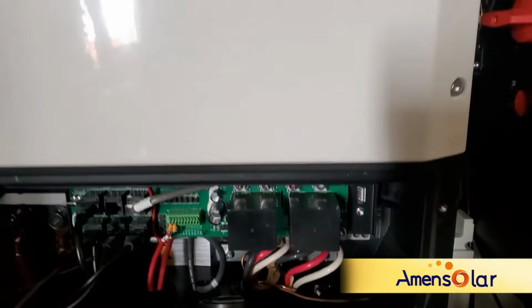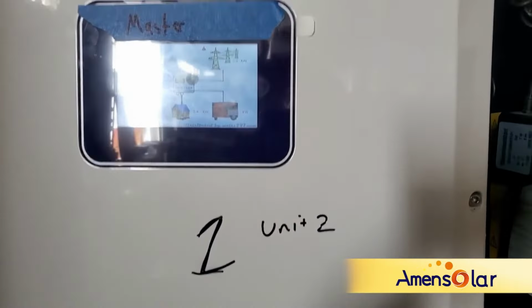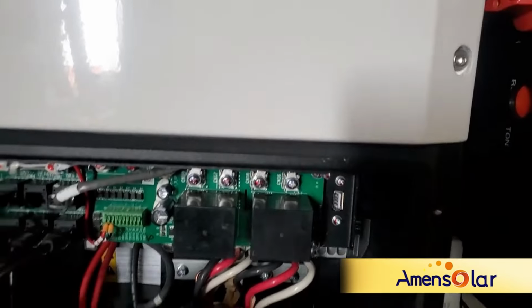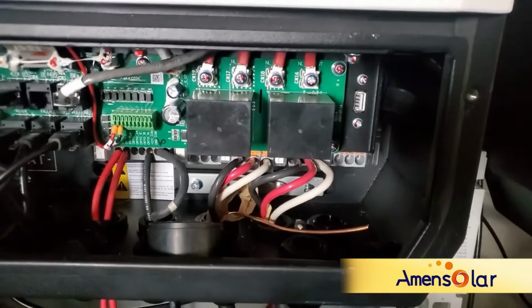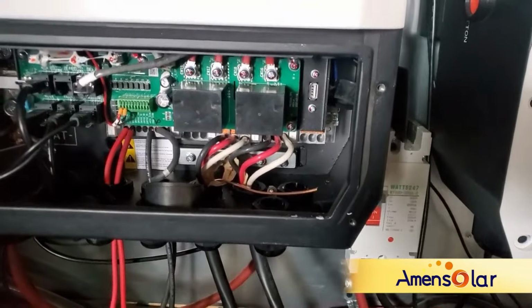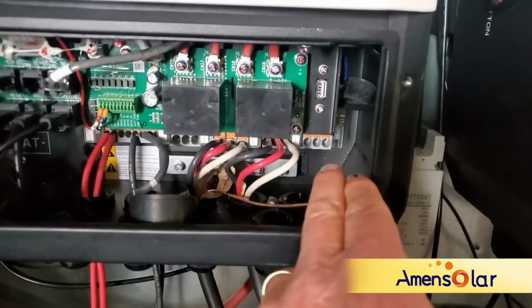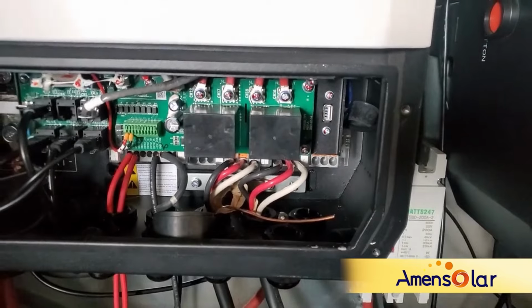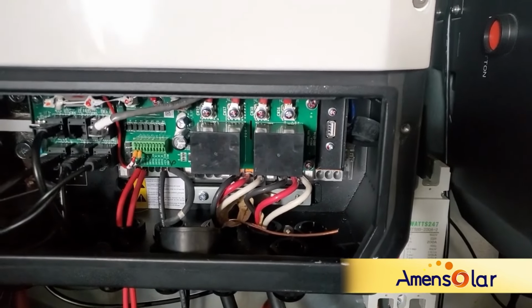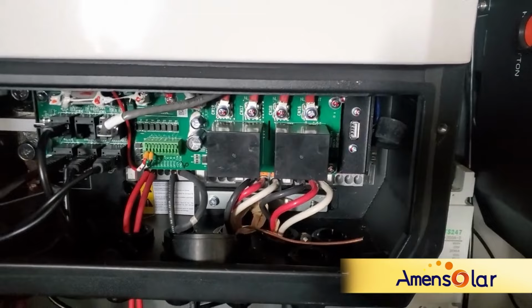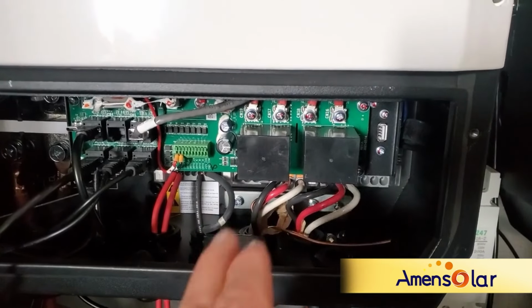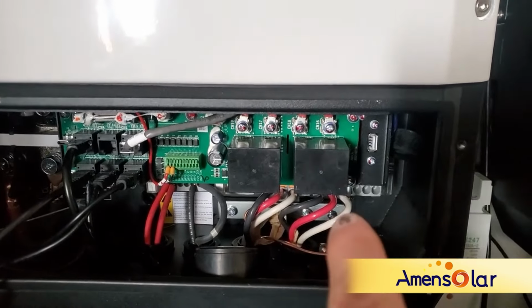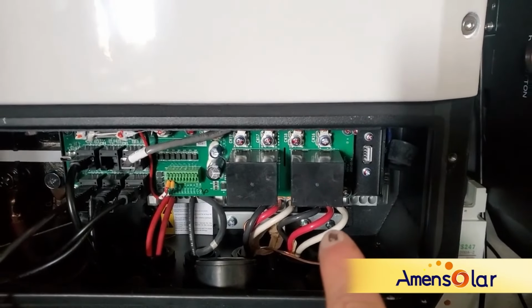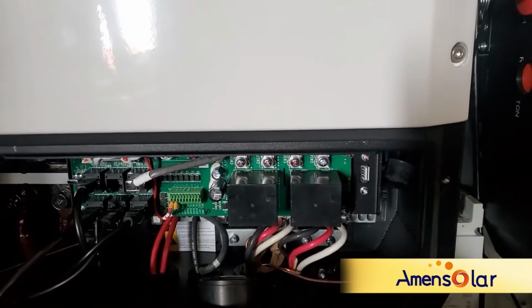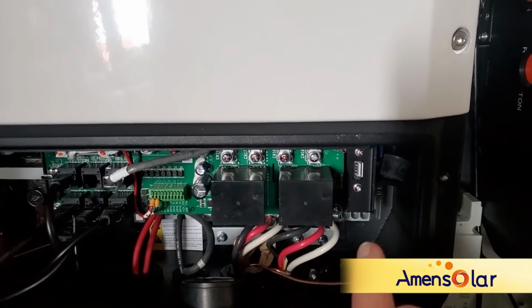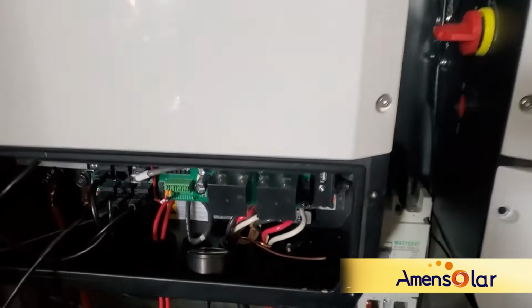And maybe I can run down there and show how that works, how to run hot water and how to use that auxiliary load. I don't think many people know how to use that auxiliary load, or if they do, the Sol-Ark doesn't. You either have to use that for the generator input or the auxiliary, so you're kind of screwed. Whereas this you can use. You've got 4 inputs, like I said. You've got generator, utility, load, 1 output, which is load, all the way through from 0 to 100% of the battery, and the other one is programmable depending on the battery percentage.